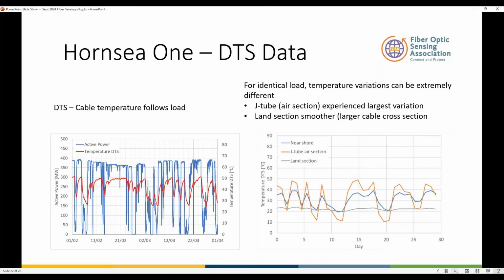The key point of this is that you are monitoring the actual temperature of the conductor itself, and you're able to identify that. In the air section, as it points out, you can see the largest variation, and the land segment has the smoothest section because that's where the cable is buried.